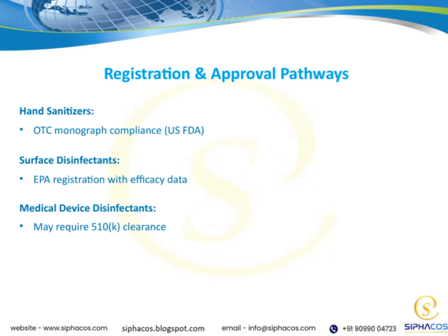For medical device disinfectants, the process can be a bit more complex. They may require 510(k) clearance, which involves submitting data to demonstrate that the product is substantially equivalent to a legally marketed predicate device. Understanding these pathways is essential, as they help us navigate regulatory requirements and bring our products to market efficiently. Each pathway is tailored to the type of product and its intended use, connecting directly to our overall goal of compliance and safety in disinfectant development.